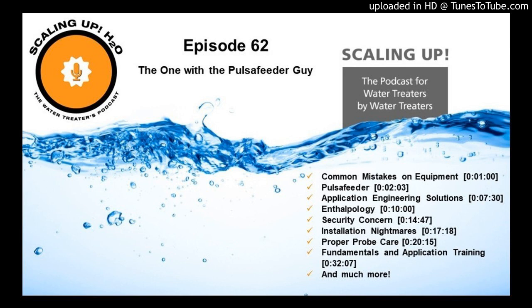And someone told me that because it's a semi-permeable membrane and you've got that reference material in there, as soon as it gets made, it starts to diminish its accuracy. So in the box, it has an expiration date. And then you put it in the system and eventually it is going to fail. And I think a lot of people don't realize that.